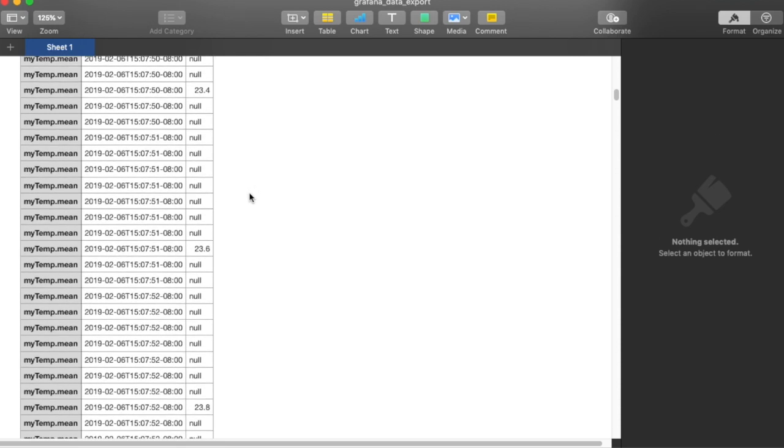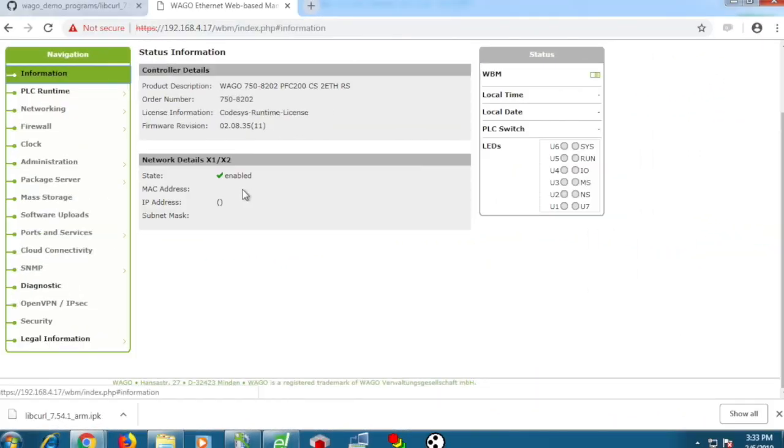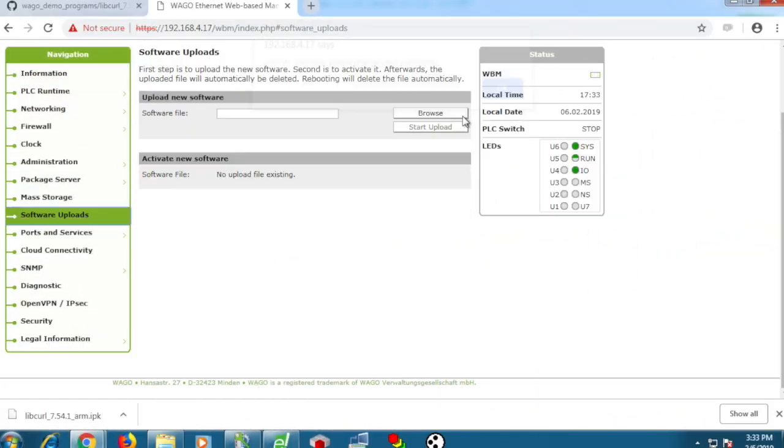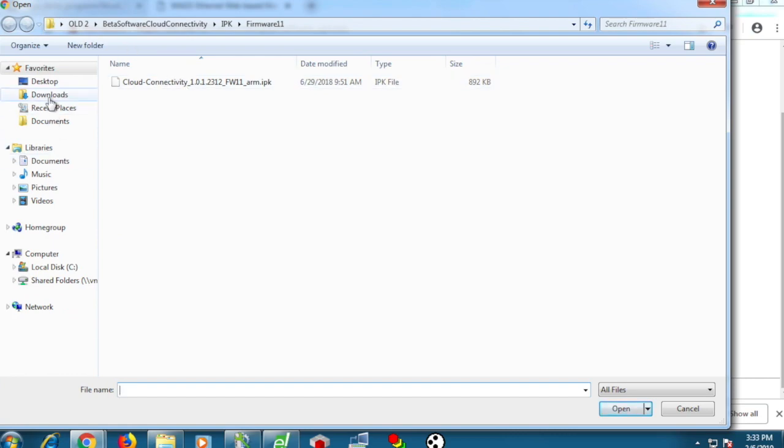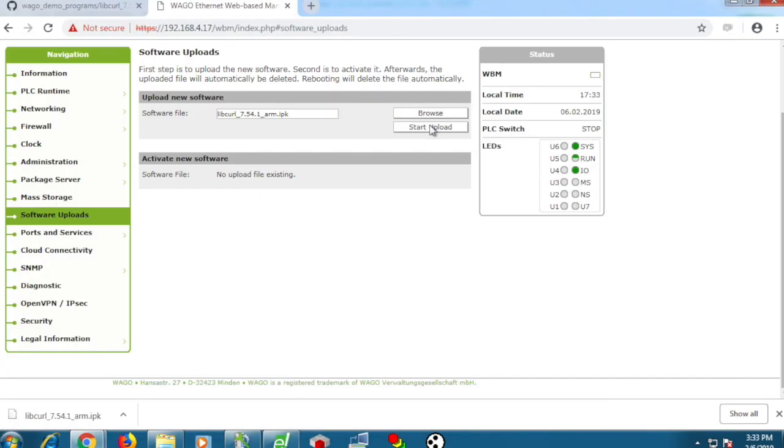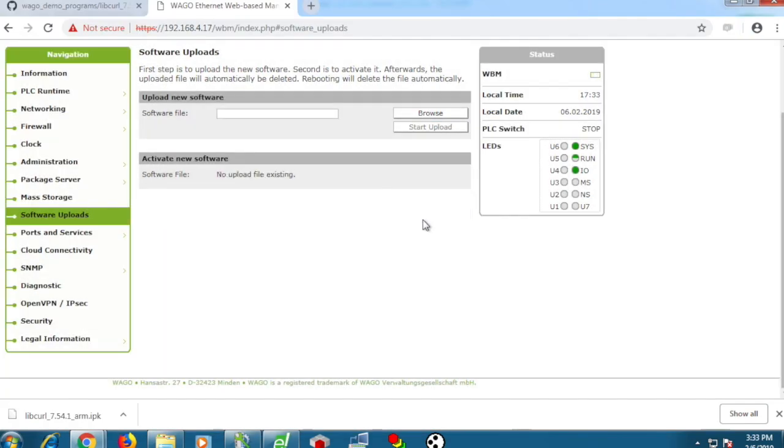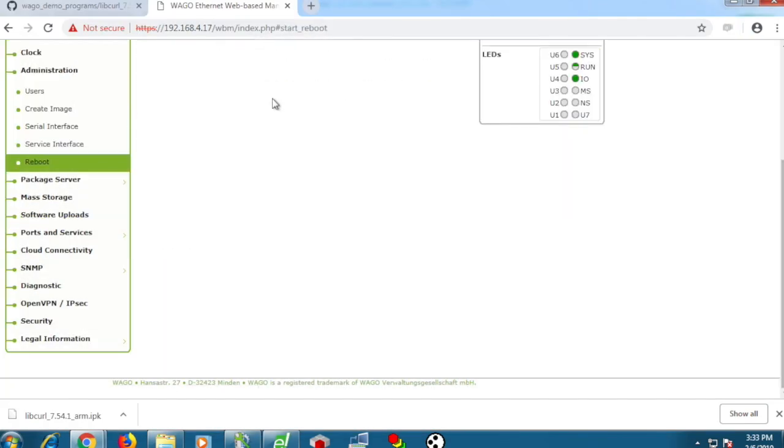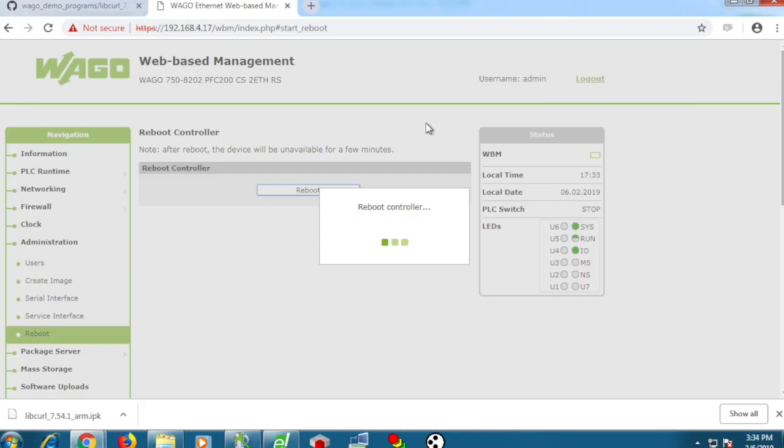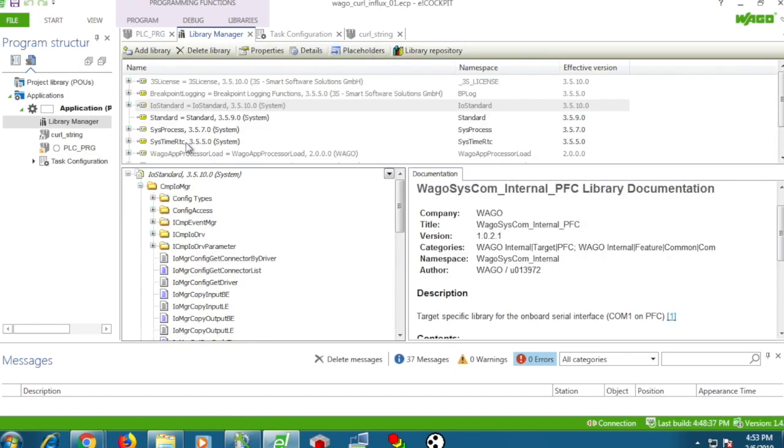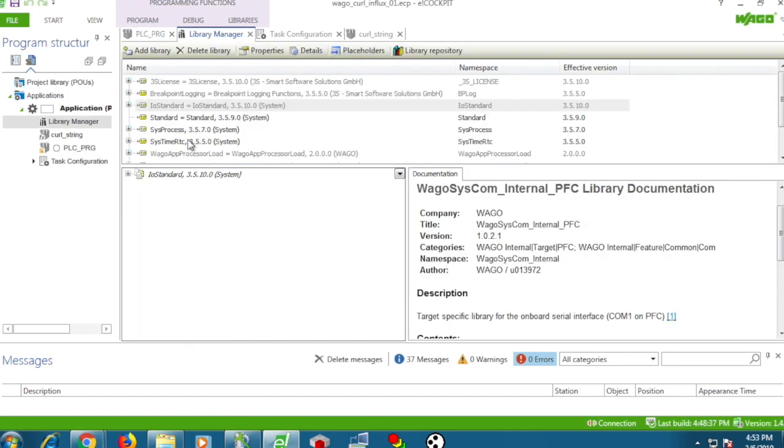Now we'll show how easy it is to use the WAGO PFC 200 to insert data into Influx. We need to start by installing curl. In the web-based management, you can upload the curl IPK and then reboot the controller. Then in eCockpit, you can see this very simple program that generates that curl command and then calls it from the Linux command line.